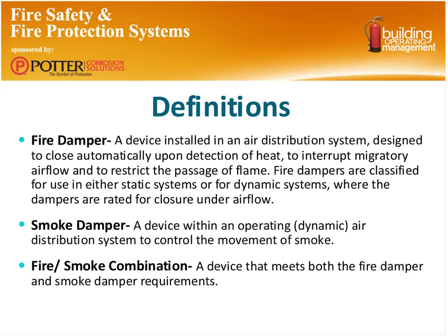All right, so now we know what we have and what we're supposed to be doing. Let's go through a couple quick definitions. What is a fire damper? Well, I'm not going to go through these real in depth, but you can always read them over later. Basically, a fire damper is a device to stop flame from migrating from one portion of a building to another. A smoke damper, same thing, trying to stop smoke moving from one area of a facility to another. There's a combination fire and smoke damper, and those devices are really intended to stop both smoke and flame spread.